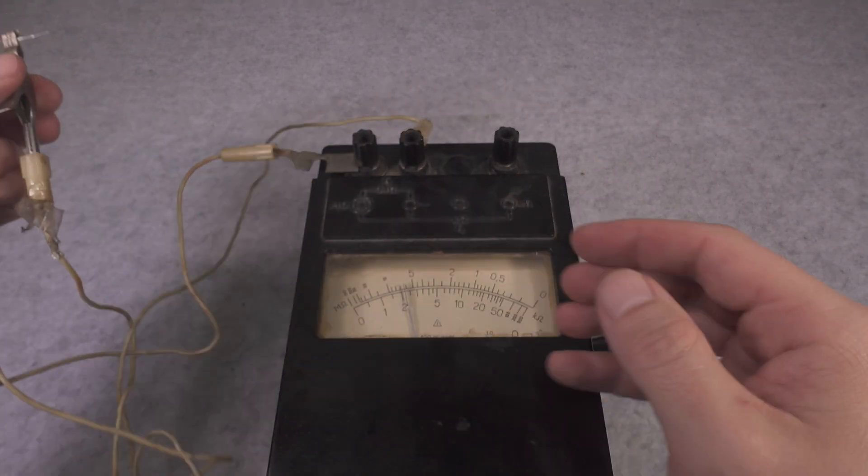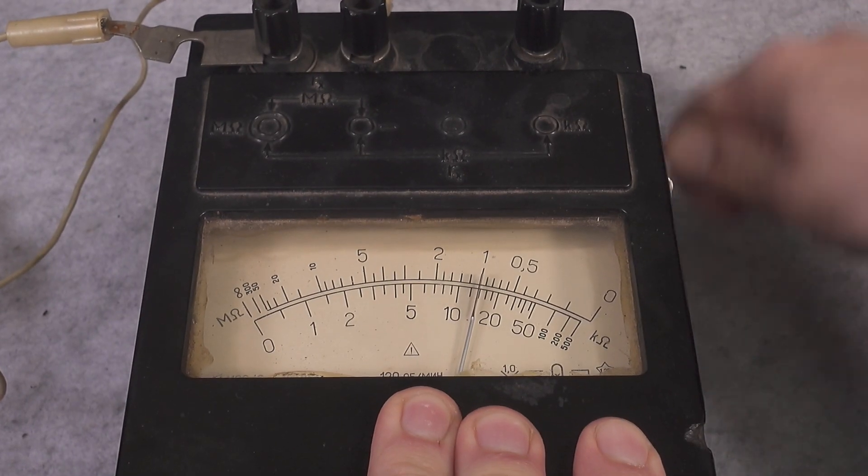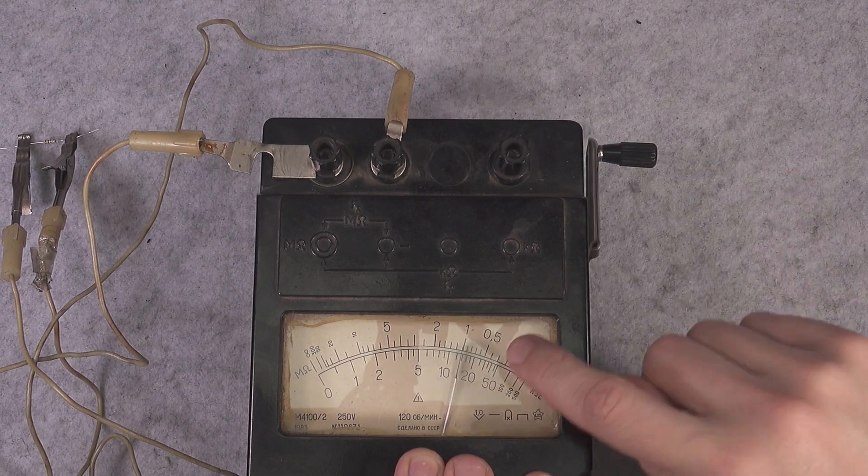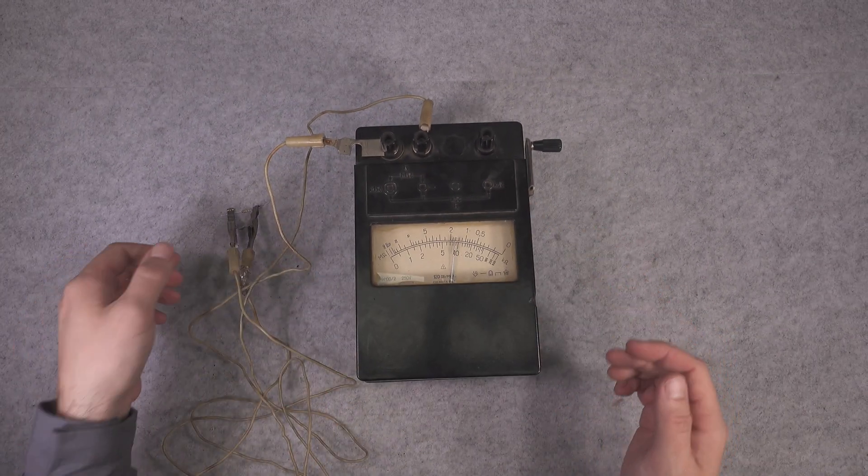To our test leads, and as before we are going to nicely crank it. And as you can see on the upper scale we've got one mega ohm. So as you can see, the device is operational.